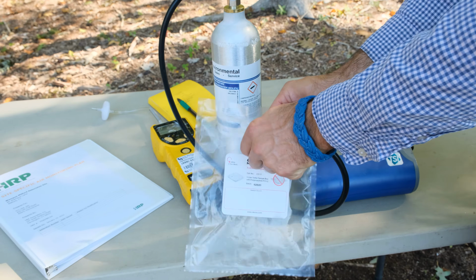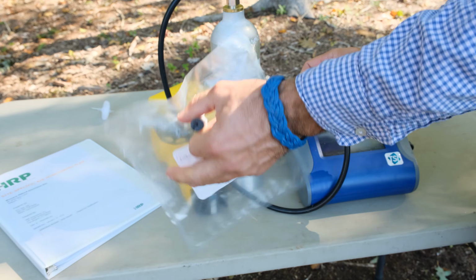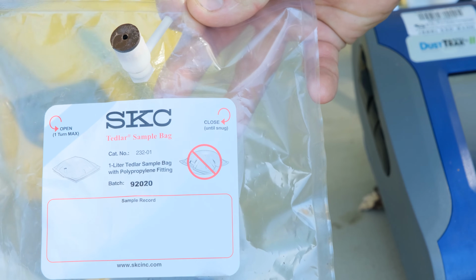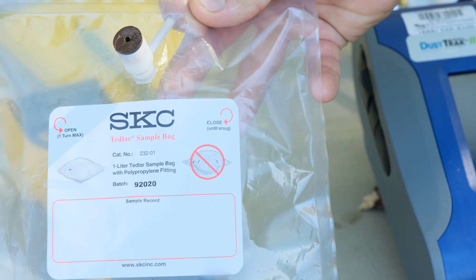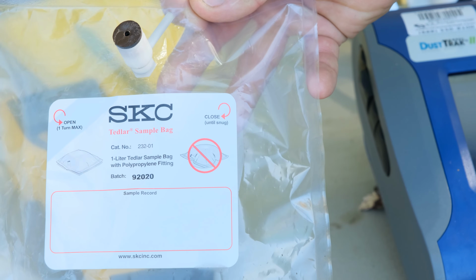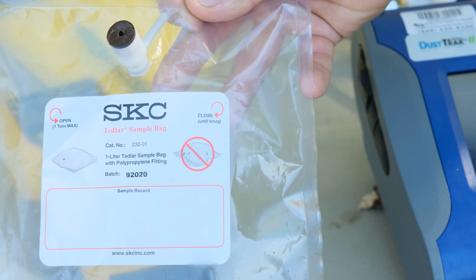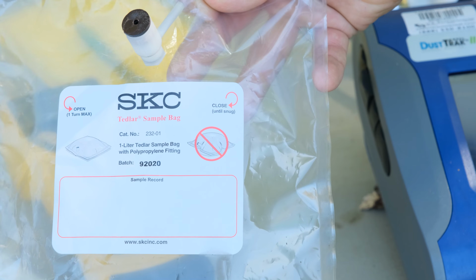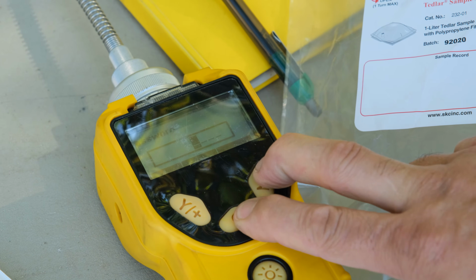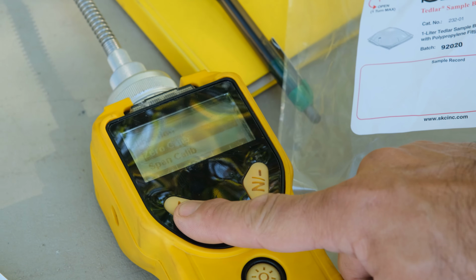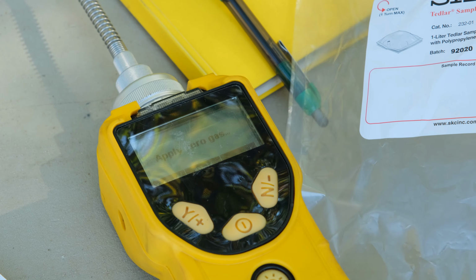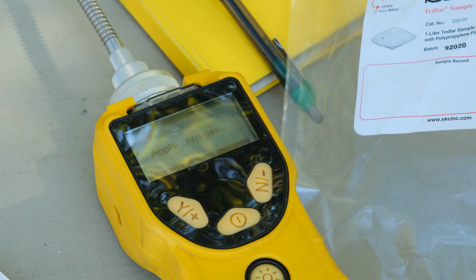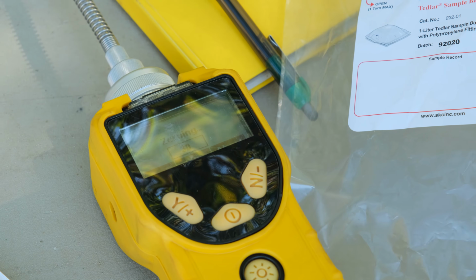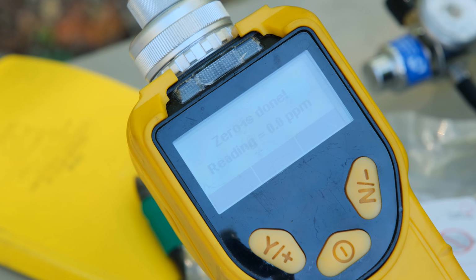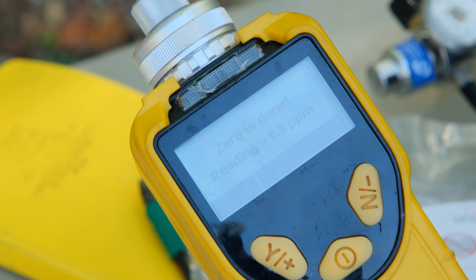Once you're about halfway full, you can go ahead and detach the Tedlar bag. Make sure you don't go over 80% volume if you're filling the bag here. There's usually an illustration, such as the one you're seeing here, to show you what an overfilled bag would be. Then you're going to enter the setup menu by holding down the 2 buttons you see here. You'll now do a 0 calibration on ambient air by selecting 0 cal and hitting that left button. Calibration usually takes between 30 and 60 seconds.